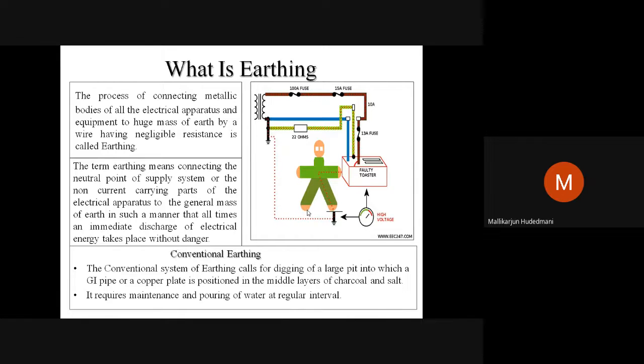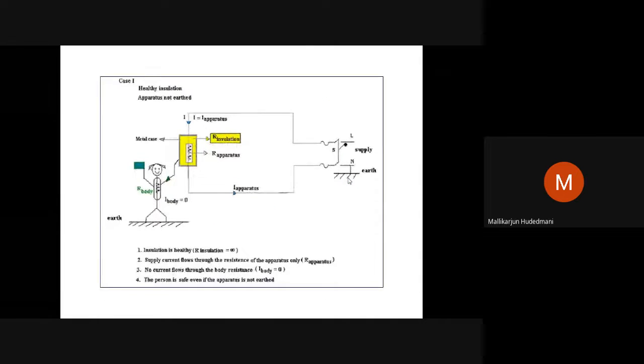So earthing provides safety for the operator. The leakage current, or additional current in the body of the metal enclosure, will be driven to the earth. So suppose this toaster is faulty and this wire is not appropriately earthed, that is how a person feels an electric shock. If it was there perfectly, he would have been able to work safely even with the faulty toaster. So in this way, we have two methods of working.